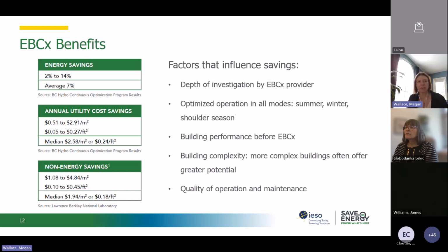Factors that influence savings are the depth of investigation by the EBCx provider, and whether you're able to optimize operation in all modes, during summer, winter, and shoulder seasons. The building performance before EBCx matters too, if you're already noticing issues or higher energy usage than a typical building, there's more opportunity for savings. Building complexity also plays a role, more complex buildings often offer more potential savings, so a laboratory might have more savings than a typical office building. And what's the quality of the operations and maintenance of the building?